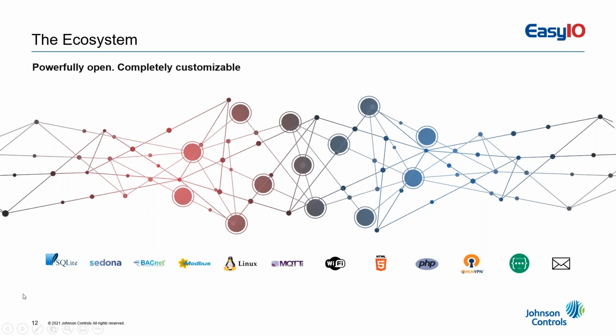That's part of the Sedona framework. Besides that, we've added the BACnet and Modbus protocols to each controller, but we've gone a step further than the competition. Looking at BACnet, we have BACnet MSTP and BACnet IP, both client and server. We do the same on Modbus with the slave and master version. And you can mix and match everything.